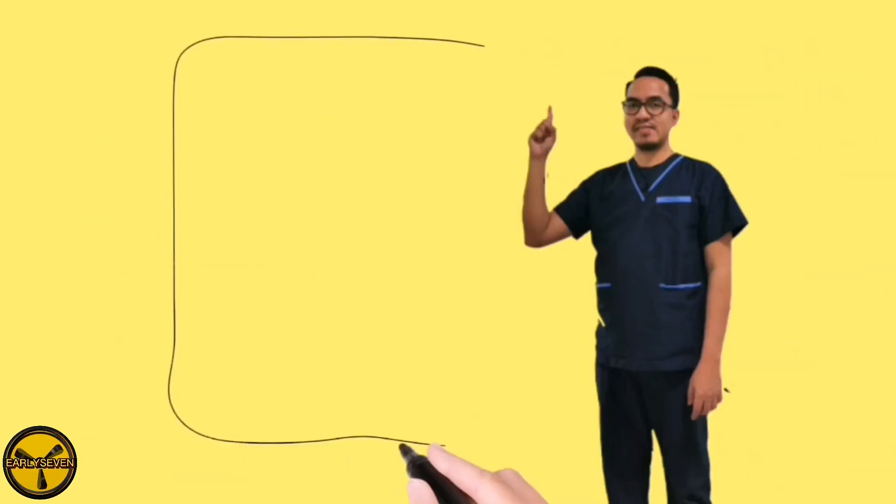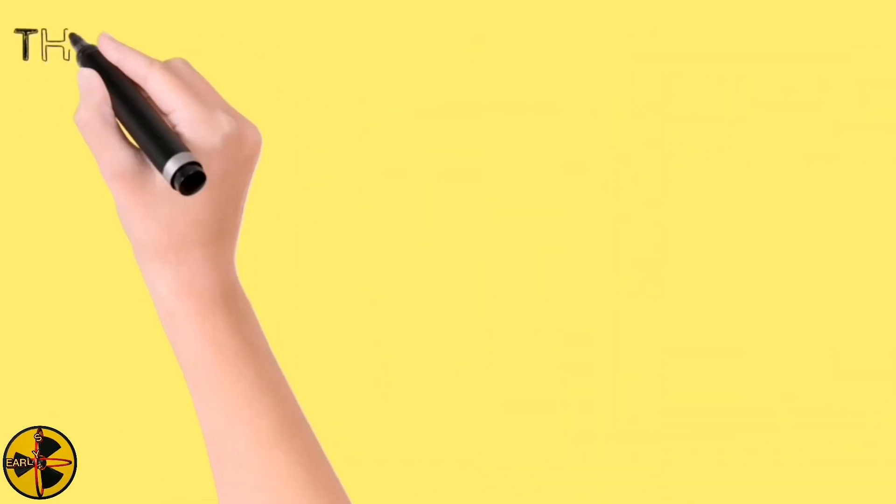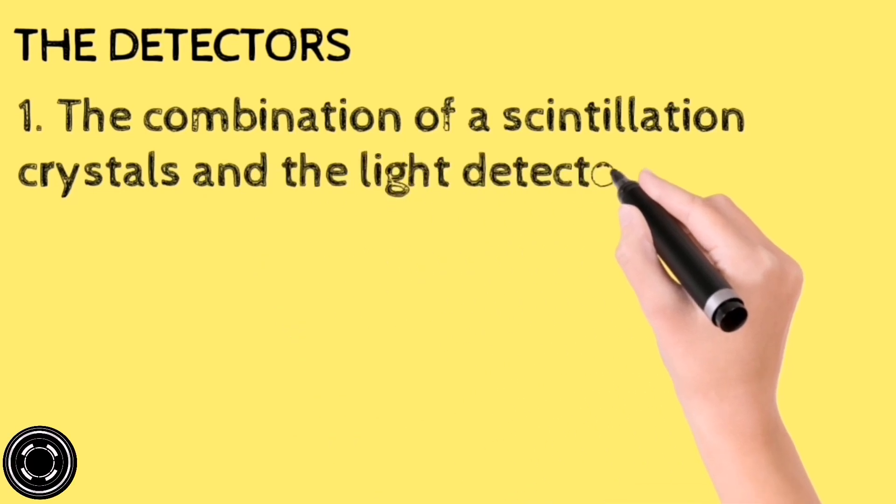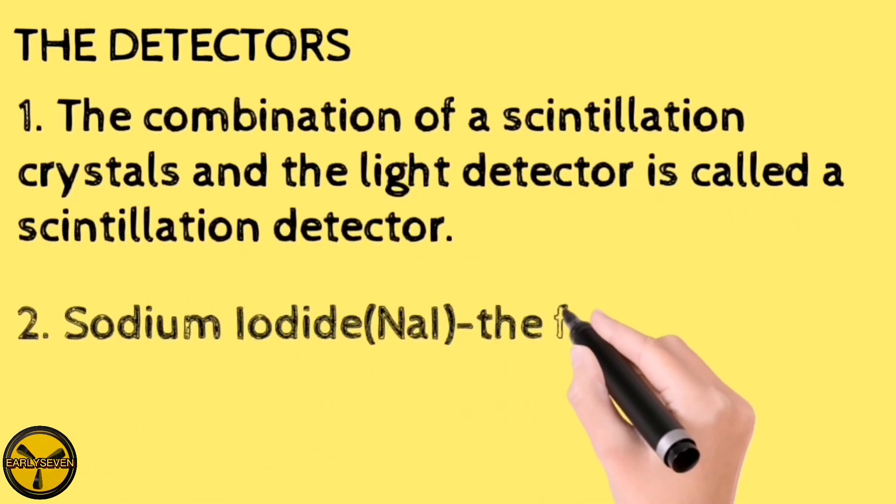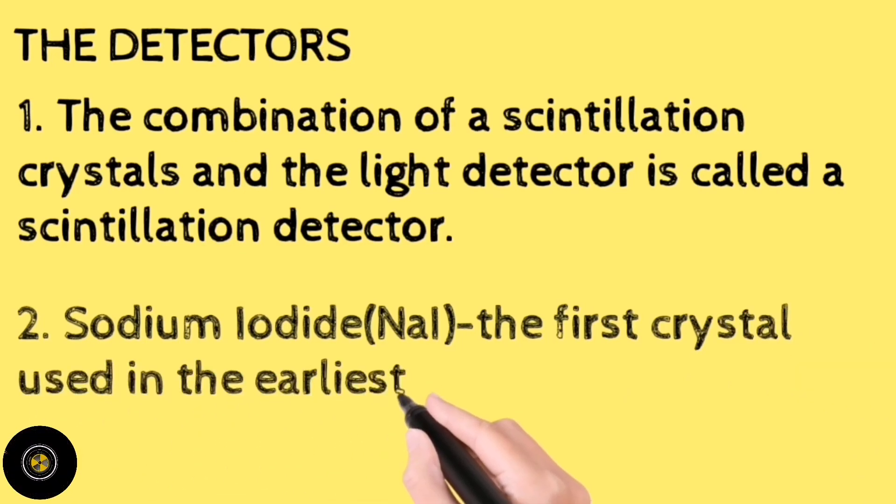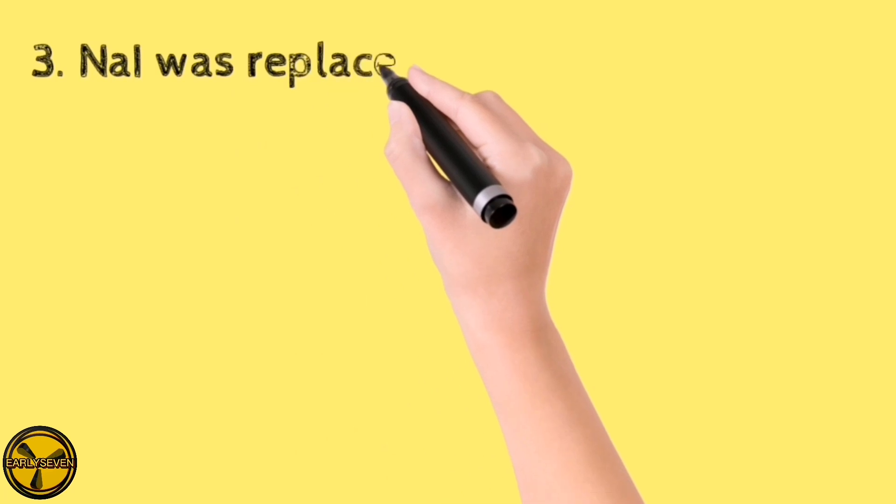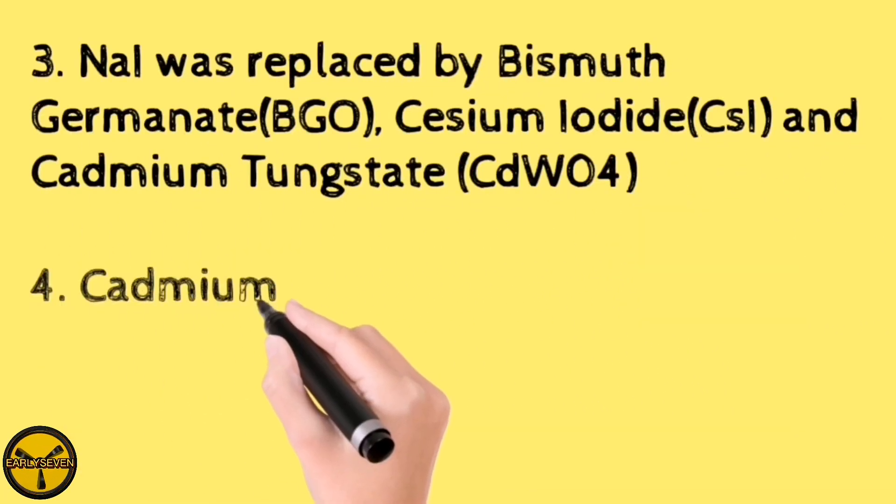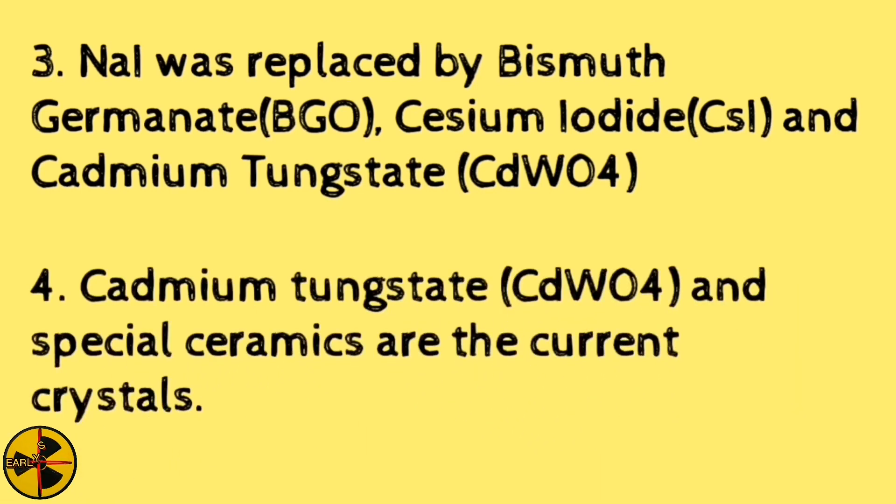The third main component of a CT scanner is the detector. The combination of a scintillation crystals and the light detector is called a scintillation detector. Sodium iodide is the first crystal used in the earliest scanner. Sodium iodide was replaced by bismuth germanate, cesium iodide, and cadmium tungstate. Cadmium tungstate and special ceramics are the current crystals.